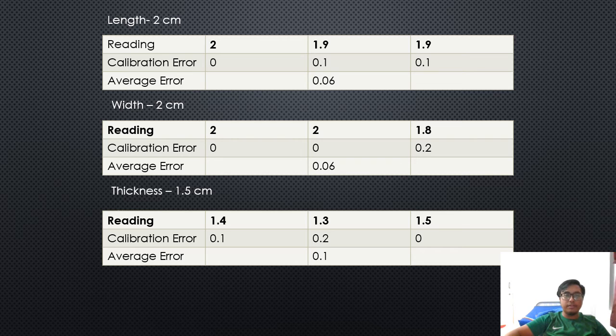After the process, we get this. We can create this table, which shows the readings of the process that we took earlier. The true length is 2 cm, and we subtract the true length from the reading that we get to obtain the calibration error. Then we add all of the calibration errors and find the average, and here the average is 0.06. The same happens with the width and the thickness, and we get calibration errors of 0.06 and 0.1. Every one of these average errors must be subtracted from the measurement that we take from the tool, because it has a calibration error.